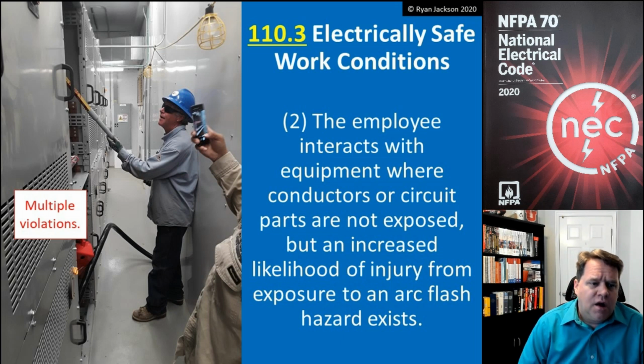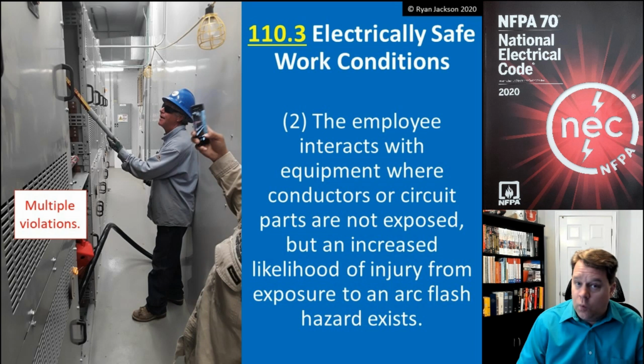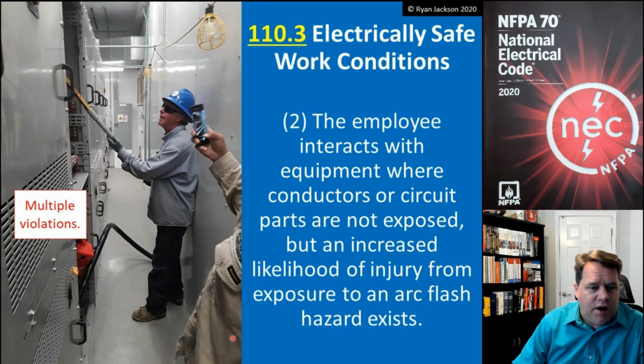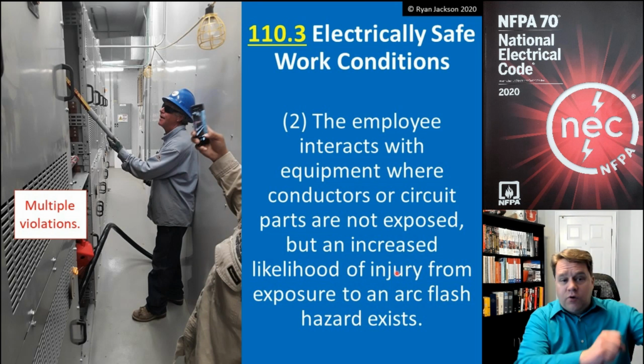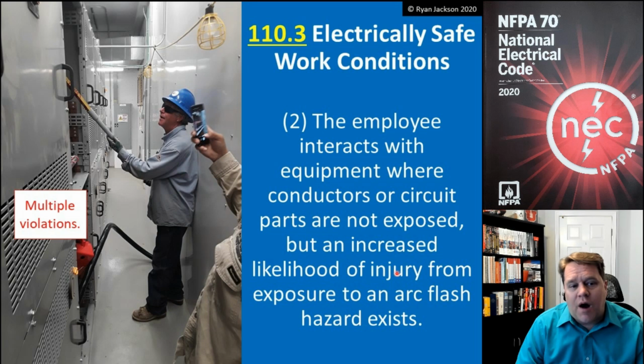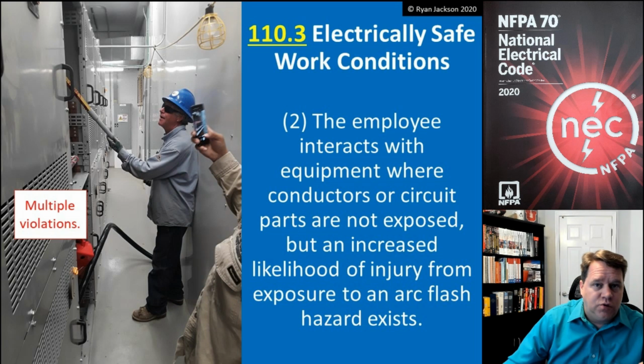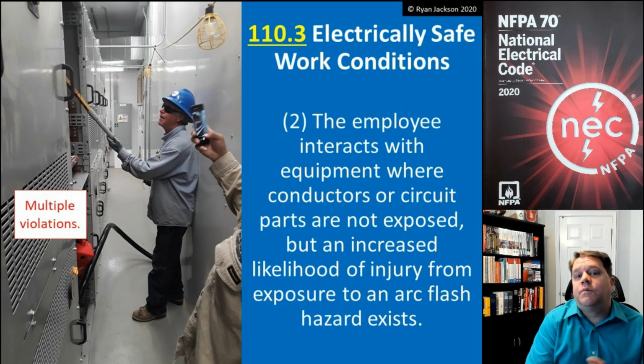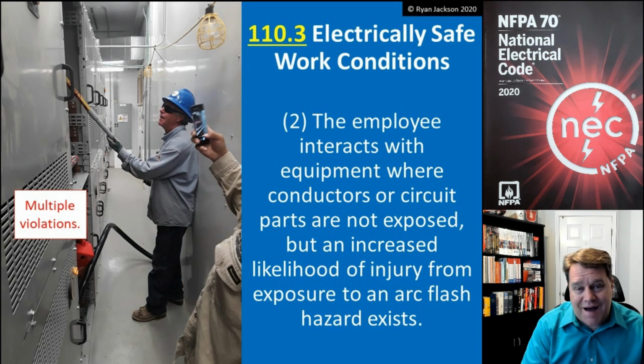All right, so we've got this individual doing whatever it is that he is doing. It looks like we don't even have the required working space in 110.26, so there's a violation of the NEC. But whatever type of work he's doing, he's got an energized switchboard here, or switchgear perhaps, and he's doing something in the back of it. That is probably an increased risk of injury. He may not be exposed directly to the energized parts, but he's doing something that increases the likelihood of something bad happening. So this should be de-energized and put into an electrically safe work condition.